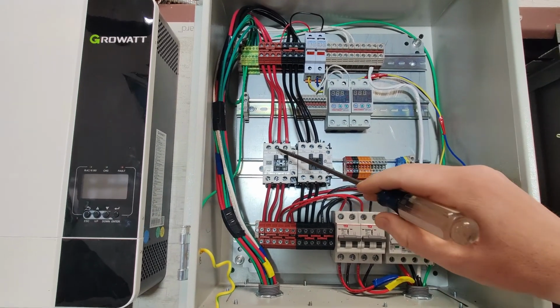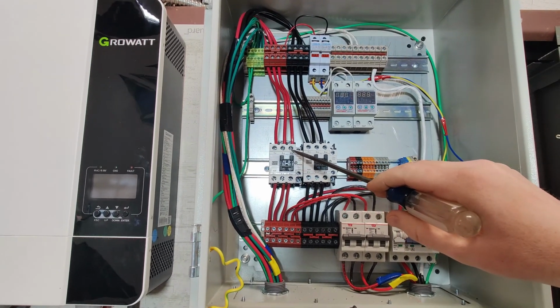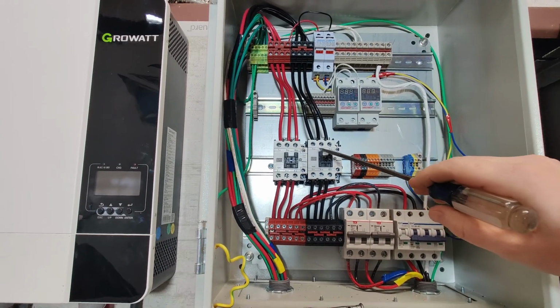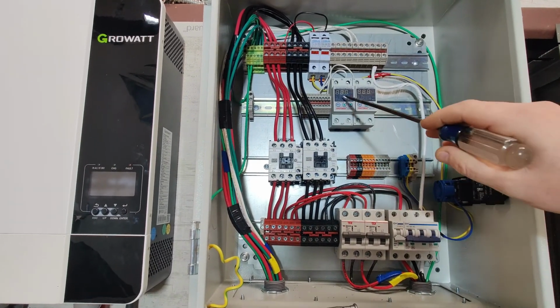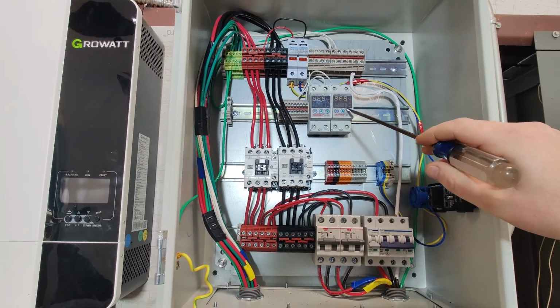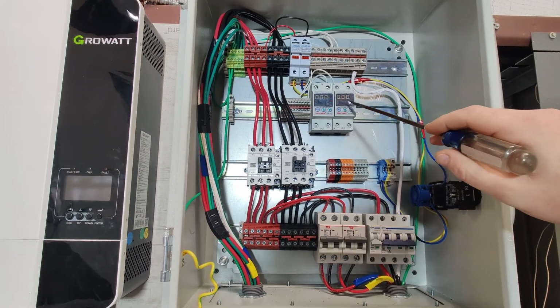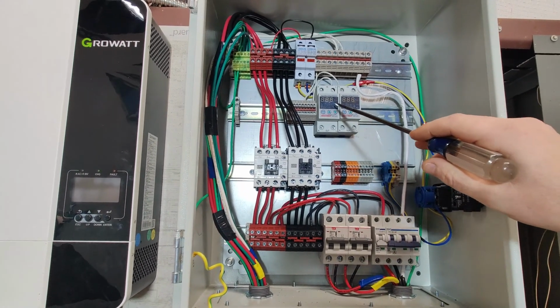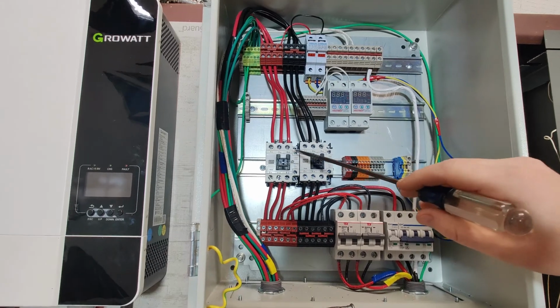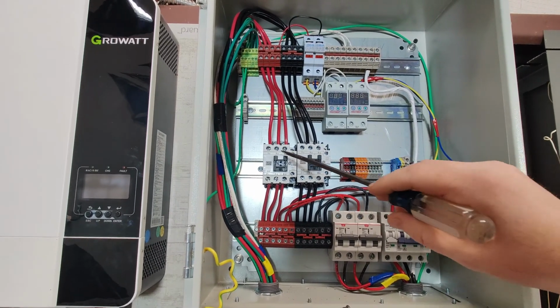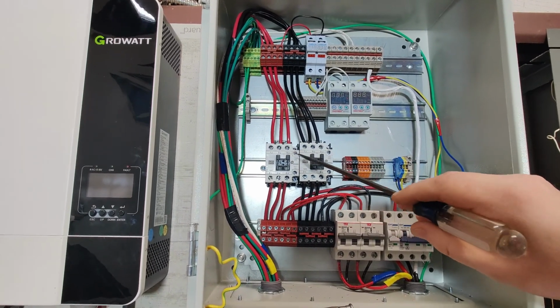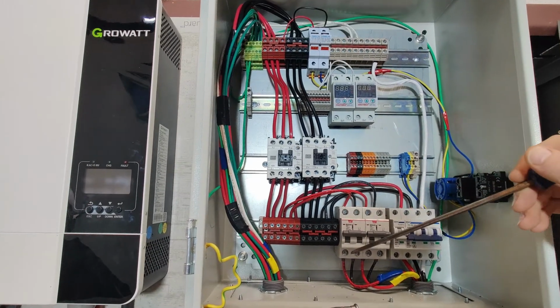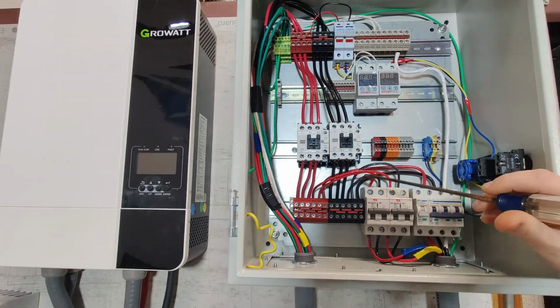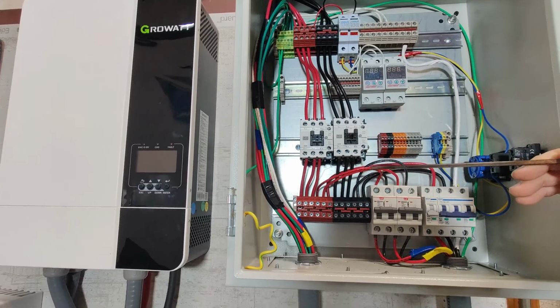So what we're doing here is switching one full leg on each contactor, and we're also monitoring each full leg on our voltage protection relays. That allows us to activate or deactivate an individual contactor.